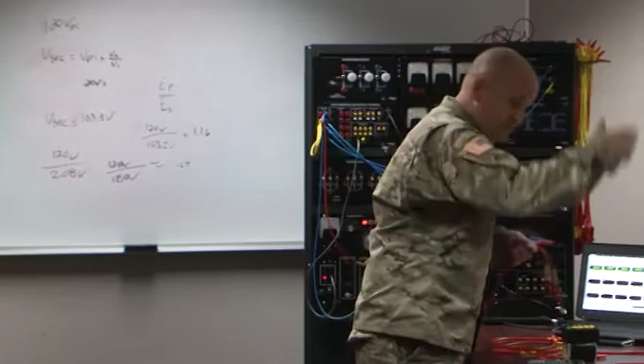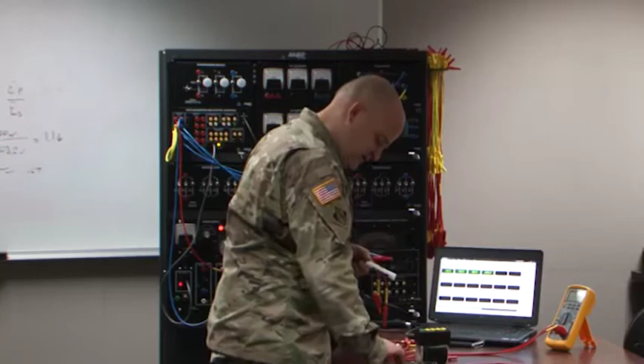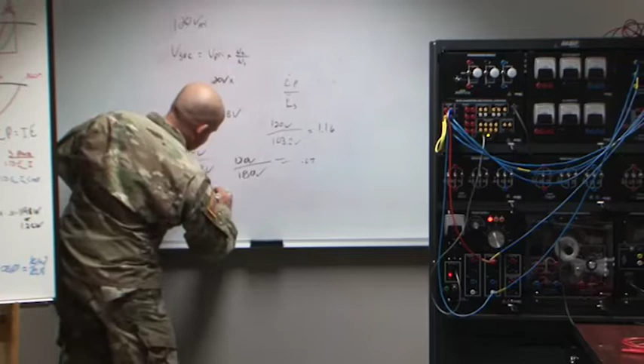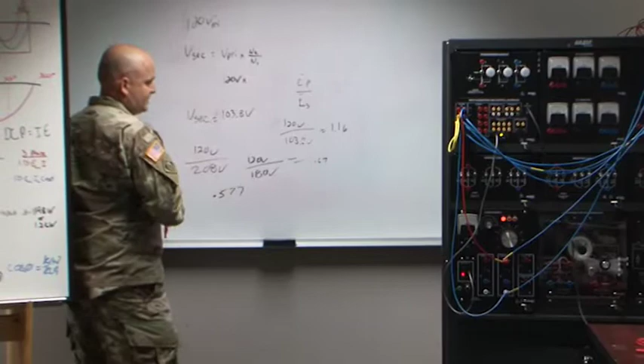So you can see the relationship between those is 1.73, although choosing 120 as the primary is going to be the inverse of that - it was 0.707, I believe. We'll see: 120 divided by 208 equals 0.577. So this one would be 0.577, or 1 to 1.73, or 1.16 to 1.